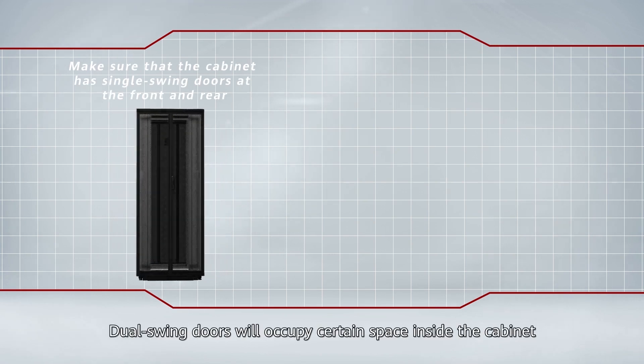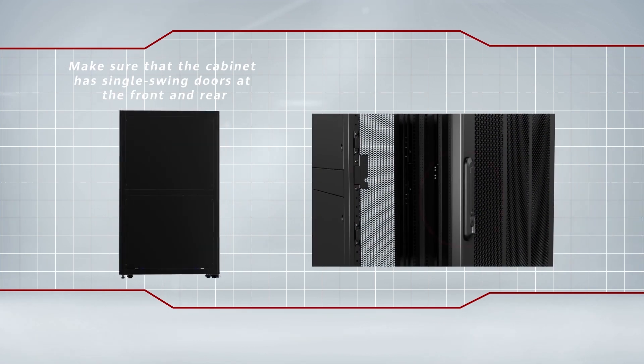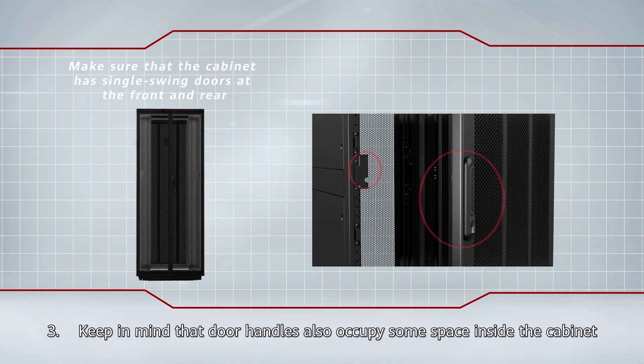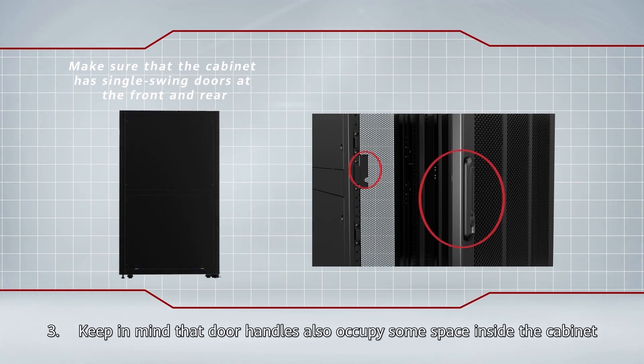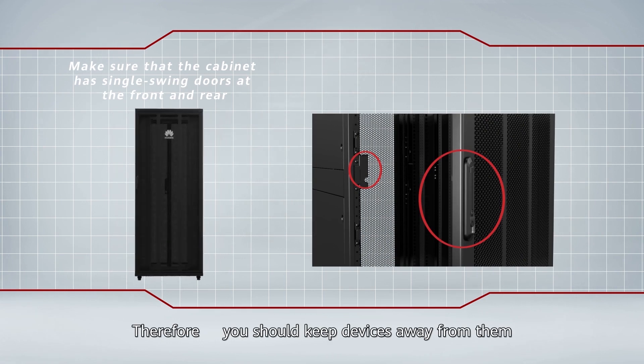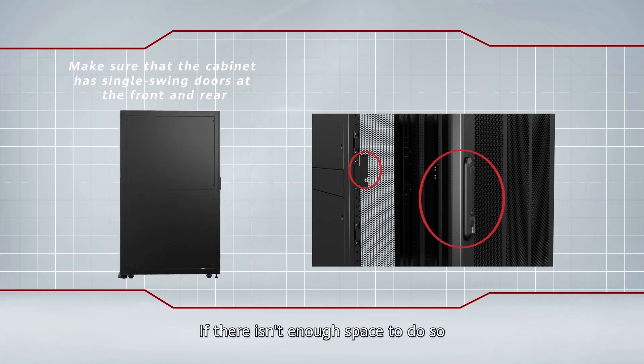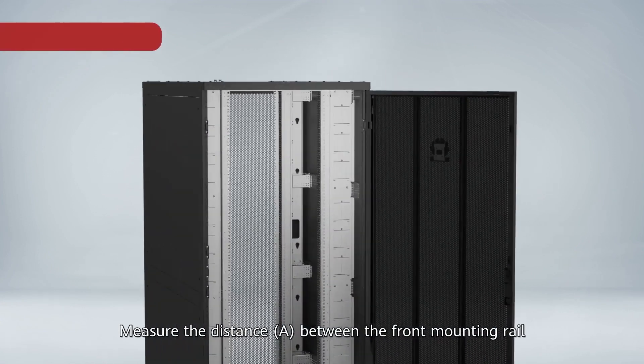Make sure the cabinet has single swing doors at the front and rear, as dual swing doors will occupy certain space inside the cabinet. Keep in mind that door handles also occupy some space inside the cabinet, so keep devices away from them when mounting. If there is not enough space, replace the cabinet.